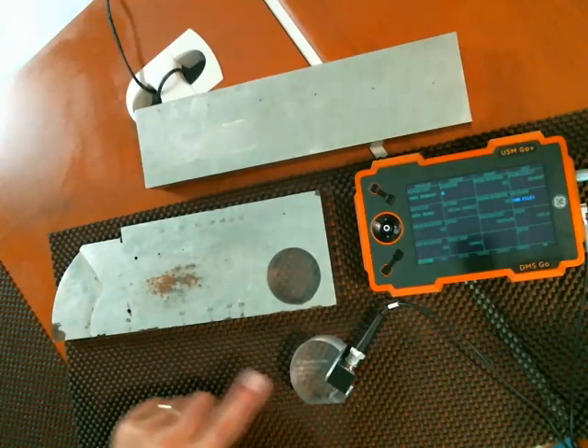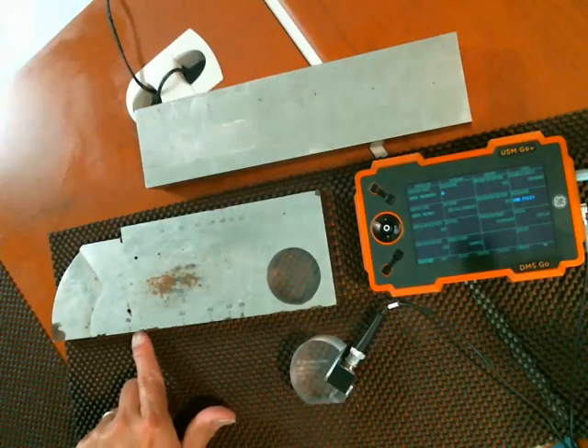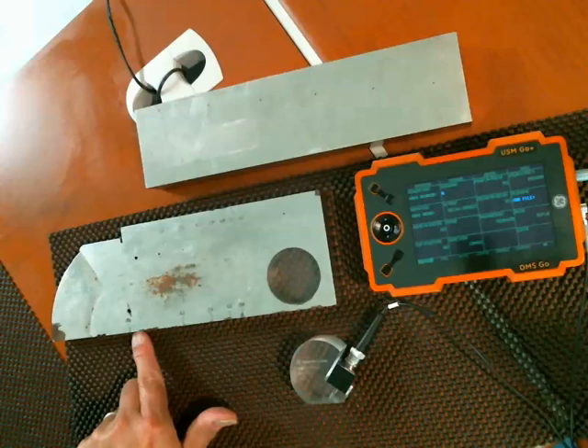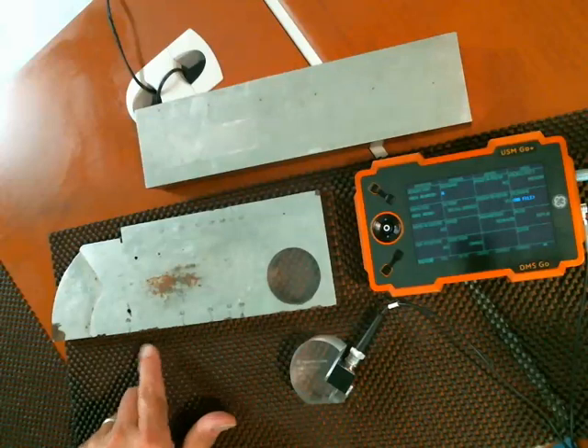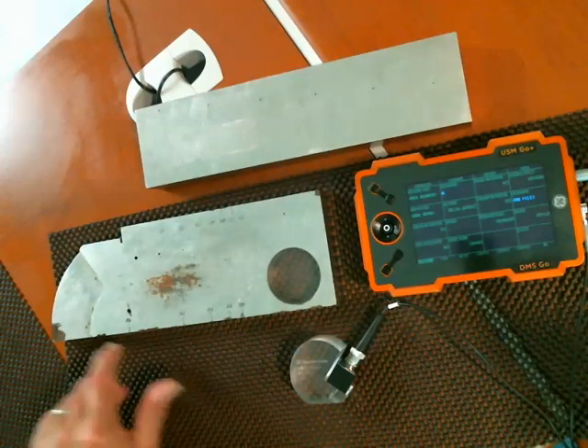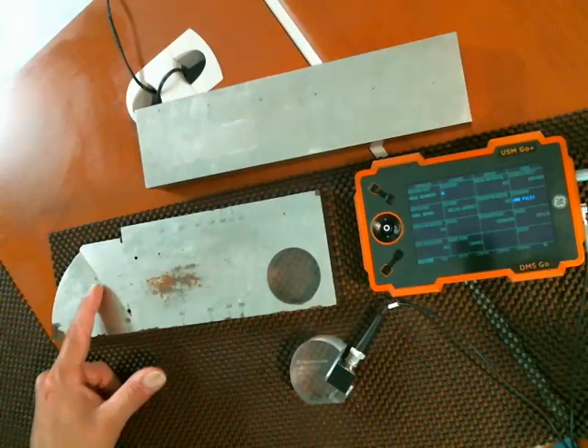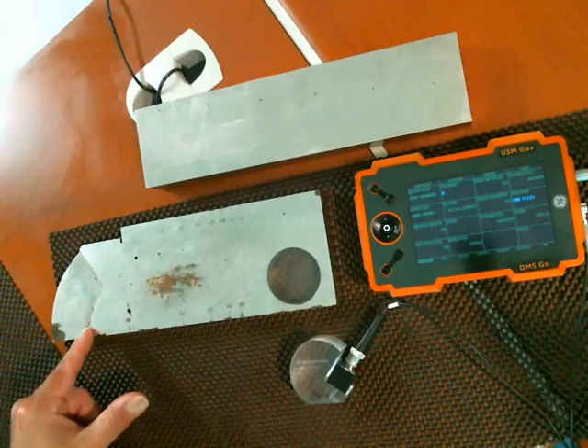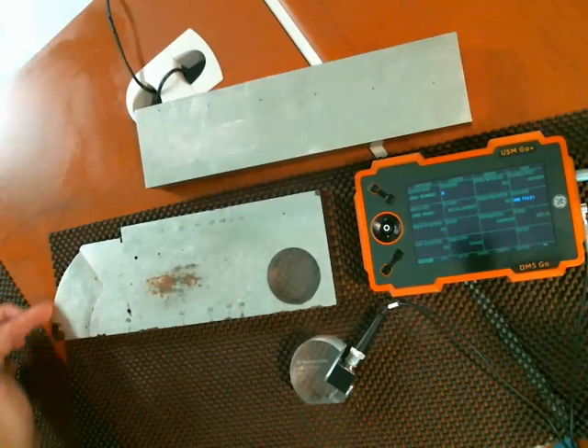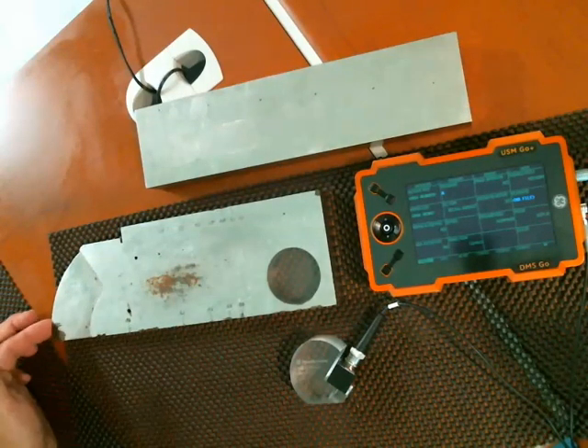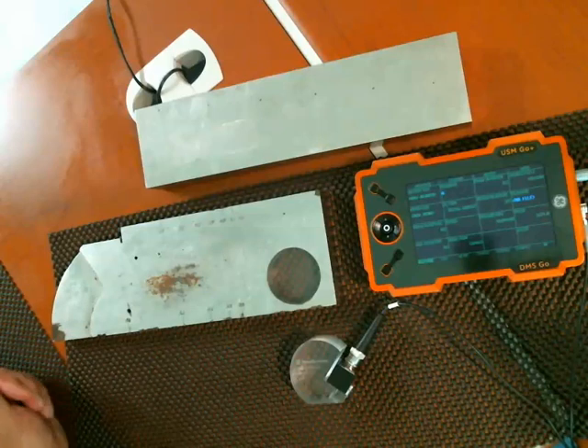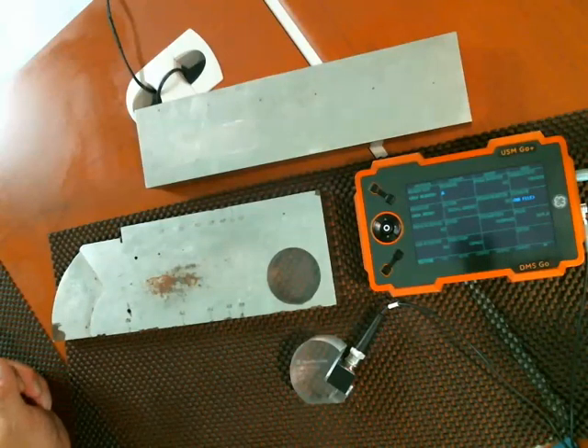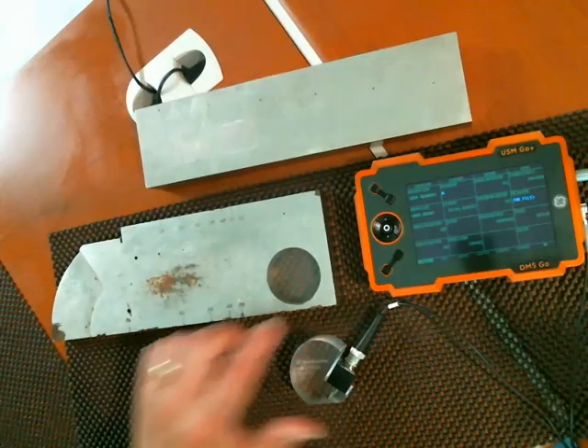When I put my angle beam probe on the block at the proper index point I have a 2 inch radius to there and a 4 inch radius to there. So we use that as part of our automatic calibration process.